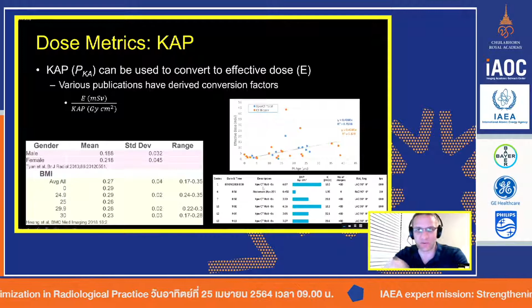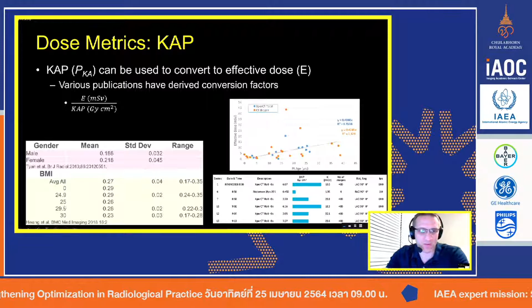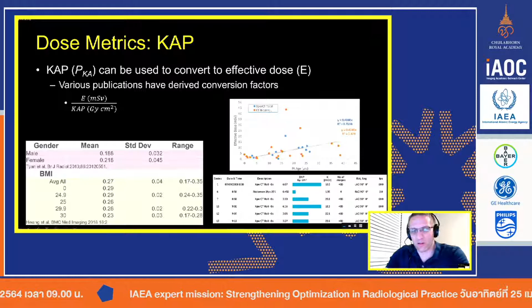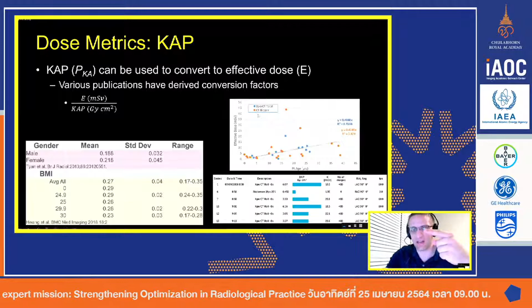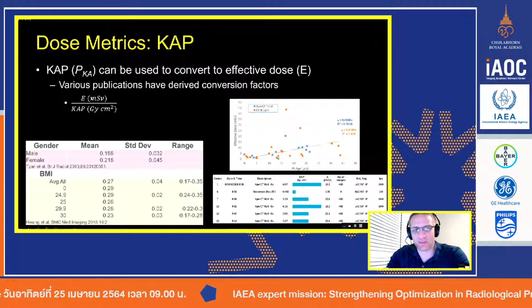And here you can see the system gives you the DAP or KAP, and also gives you the air kerma values, etc. And so here I can take all of these values and I could either sum them all up as just an average, or I could sum them all up as a total. I could average them if I really wanted to, or I could calculate this effective dose for each one of them. But either way, for the most part, you can just take this value from your dose summary report, find the equivalent conversion factor based on either gender or size, and make a simple multiplication. And here, this is just a simple plot where I was doing some work where we were comparing the CT doses from the fluoro C-arm rotation and the CT doses from a standard traditional CT scanner, which we're actually going to talk about later today. And so you can apply these correction values as long as you have a DAP or a KAP.